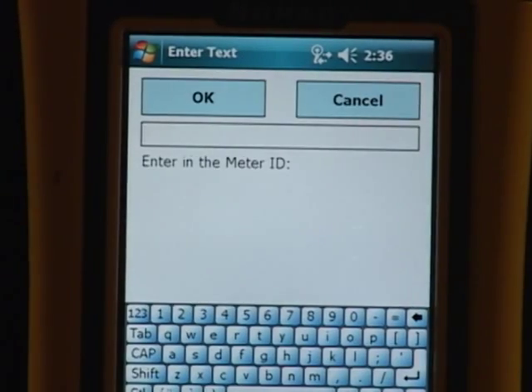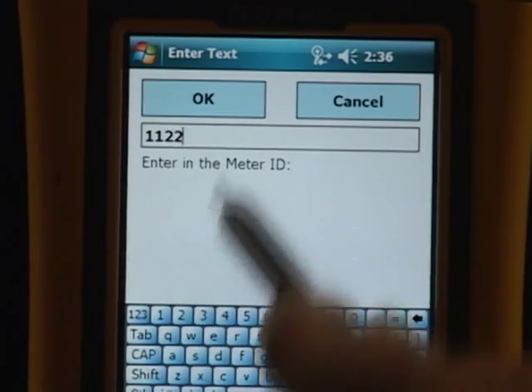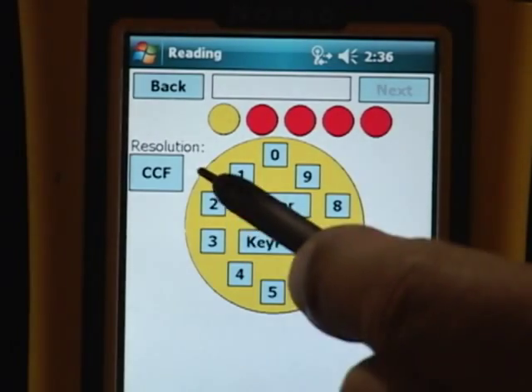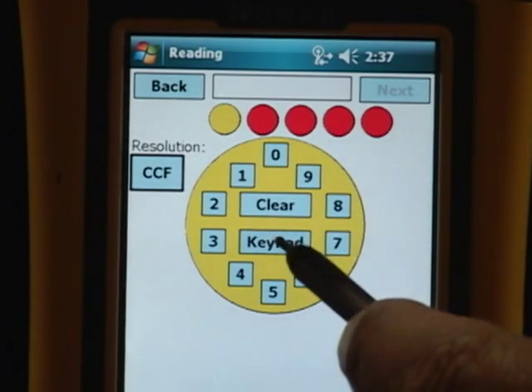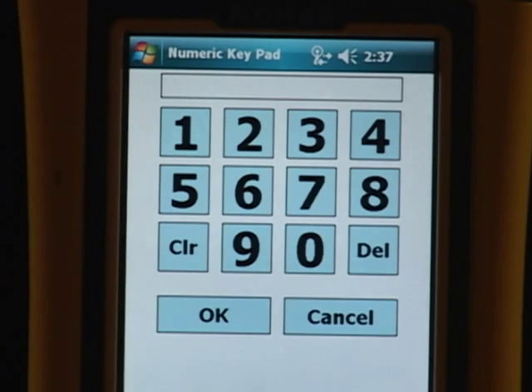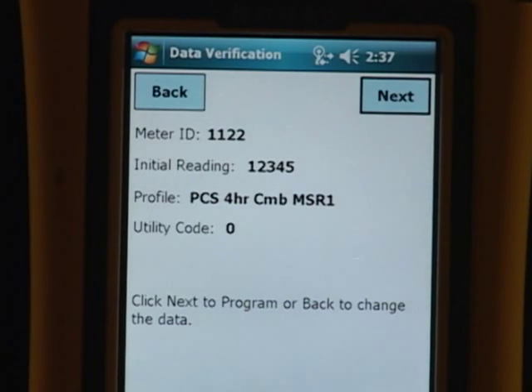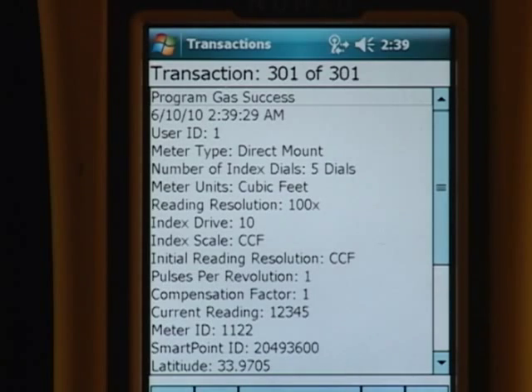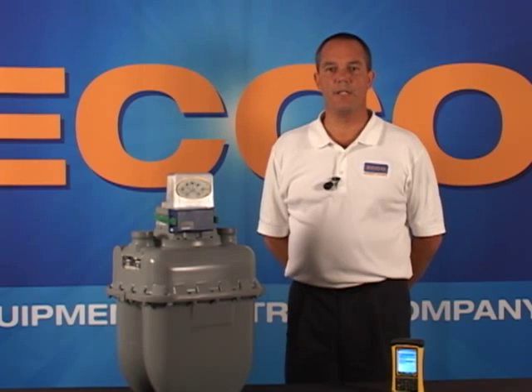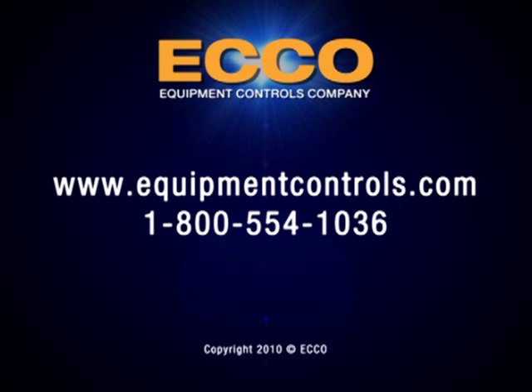Hit the next key. Enter in the meter ID, which is located on the side of the gas meter. Select the resolution as CCF. Hit your keypad. Enter the index reading. Select OK. Select Next. Hit Next again. This is the last chance you have to confirm your readings are correct. Select Programming and wait approximately one to two minutes for the programming tool to show successful. For any additional information on Sensus Gas SmartPoints, please contact us at EquipmentControls.com.